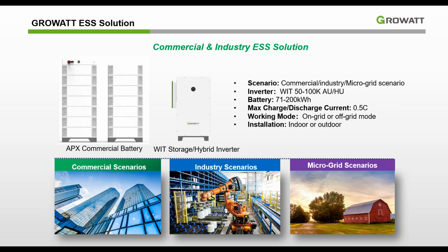Next is Growatt's biggest commercial system now. In the middle, you can see the WIT with storage hybrid inverter, and on the left is the APX commercial battery. The inverters called WIT range from 50 to 100 kilowatt, and we provide AC coupled UPS and hybrid UPS function. For batteries, each battery is 14 kilowatt hour, but the whole system capacity can be from 71 up to 200 kilowatt hour. Since the battery is 0.5C, similar to the APX high voltage battery, each 14 kilowatt hour battery means 7 kilowatt charge and discharge for one battery. And since it has IP66, it is suitable for both indoor and outdoor installation.